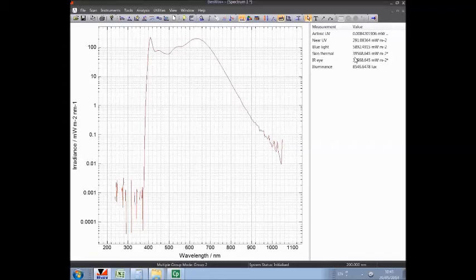Were this a larger source for which I ought to have performed a measurement with a 20 millimeter aperture, but in the first instance did a measurement with no aperture in place, and see that the blue light level is below 780 milliwatts per meter squared, then in measuring the whole source, since I'm below the limit, clearly in measuring with a 20 millimeter aperture in place, I would be equally below the limit. And one can use this as a means to not have to do this 20 millimeter aperture measurement, which may be difficult in terms of aligning the aperture and placing the aperture in front of the source.